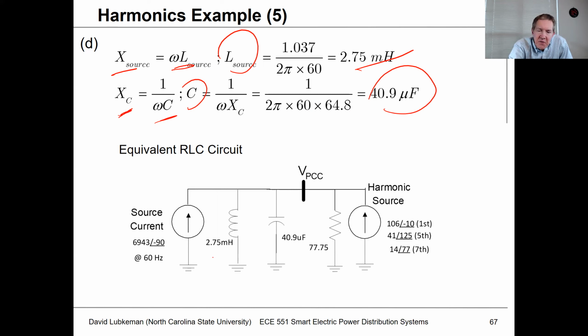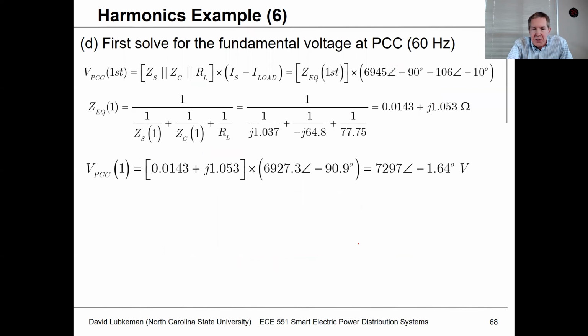So as far as individual components now, these are going to be the inductance, the capacitance, and the resistance. And now I can calculate the equivalent impedance at different frequencies. And so if I'm doing this at the fundamental, what I do to get the voltage at the point of common coupling, I calculate the parallel impedance and I multiply this by the net injected current, the source current minus the load current.